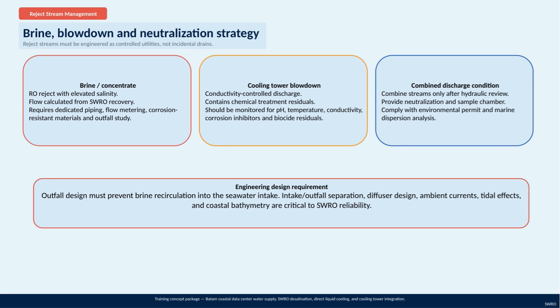Managing this brine requires dedicated piping that can handle corrosion, precise flow metering, and a thorough outfall study to ensure proper dispersal in the marine environment. Next, cooling tower blowdown is controlled through conductivity to regulate its discharge. It contains chemical residuals from water treatment, so continuous monitoring for pH, temperature, conductivity, corrosion inhibitors, and biocides is essential to keep everything within safe limits.